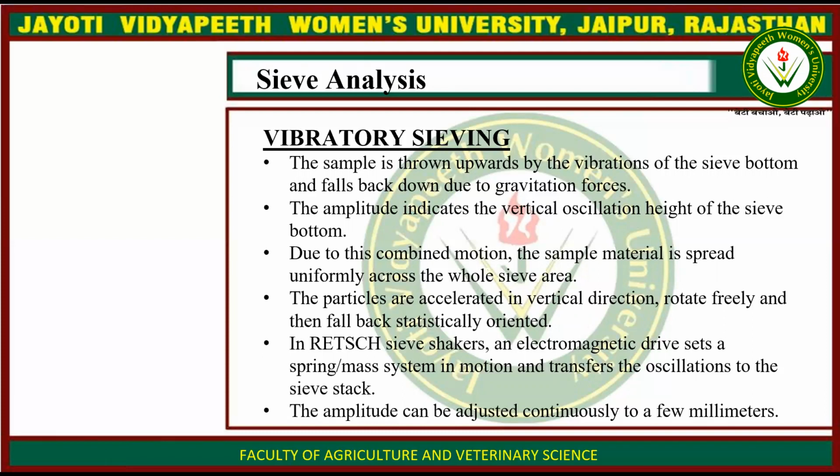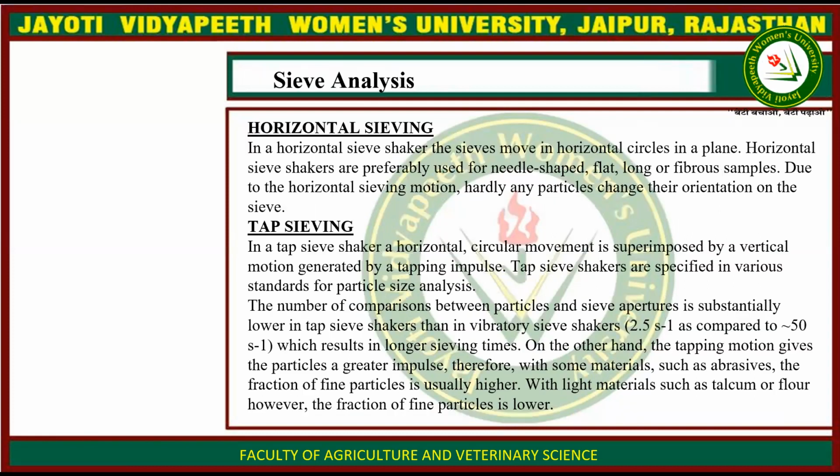In the Retsch sieve shakers, an electromagnetic drive sets a spring mass system in motion and transfers the oscillation to the sieve stack. The amplitude can be adjusted continuously up to a few millimeters.